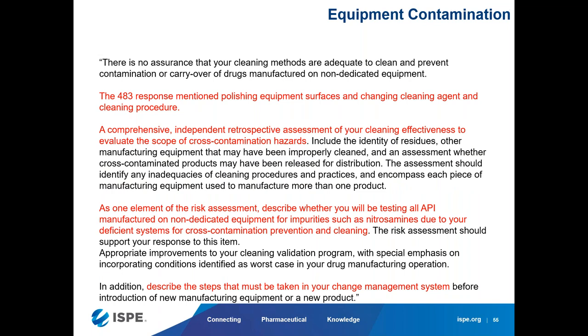The FDA cited them on equipment contamination. This FDA response mentioned polishing equipment surface and changing cleaning agent and cleaning procedure. No, they don't want to see that. They want to see a very comprehensive independent retrospective assessment of cleaning effectiveness.